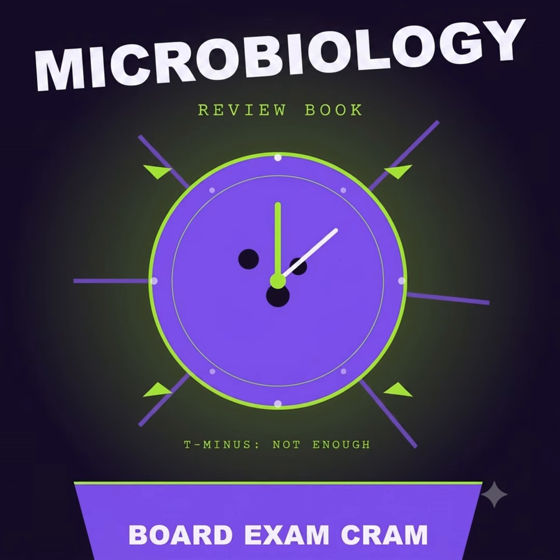The laboratory manager is auditing your autoclave logs to ensure the equipment is legally compliant and effectively achieving sterilization. You must provide the biological indicator records. Right. Which specific organism is utilized universally as the quality control standard to prove autoclave efficacy? A. Bacillus stearothermophilus, B. Staphylococcus aureus, or C. Pseudomonas aeruginosa. We need the toughest bug on the block, the heat-loving spore former. That is A. Bacillus stearothermophilus.